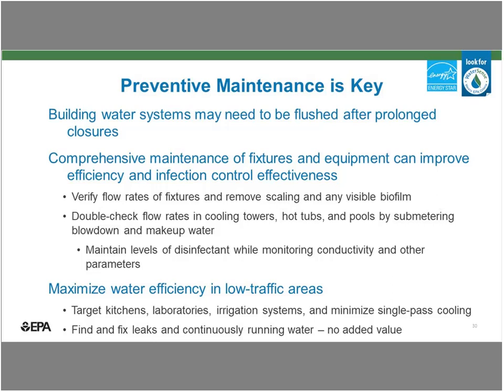You also want to double check your flow rates in your cooling towers, pools, and hot tubs by submetering the makeup and blow down water. At the same time you can check your disinfectant levels and monitor conductivity and other parameters for these systems.